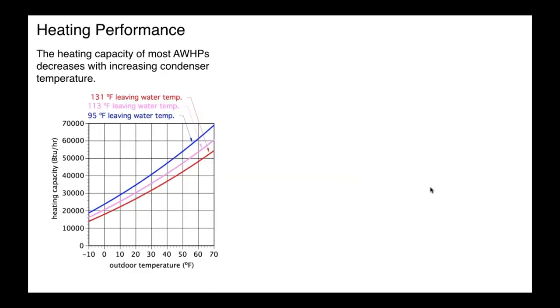Now, a typical air-to-water heat pump, its performance is strongly dependent on outdoor temperature. So you can see on the lower axis here that the heating capacity of this particular heat pump is more than double at warm outside temperatures like 60, 70 degrees compared to what it would be at minus 10. The other thing that affects the performance is the condensing temperature. The higher the water temperature that the heat pump is producing, the lower its heating capacity. And this just goes back to fundamental thermodynamics of heat pumps.